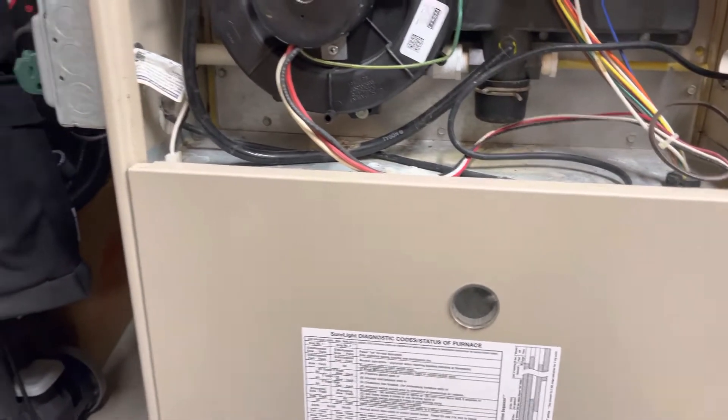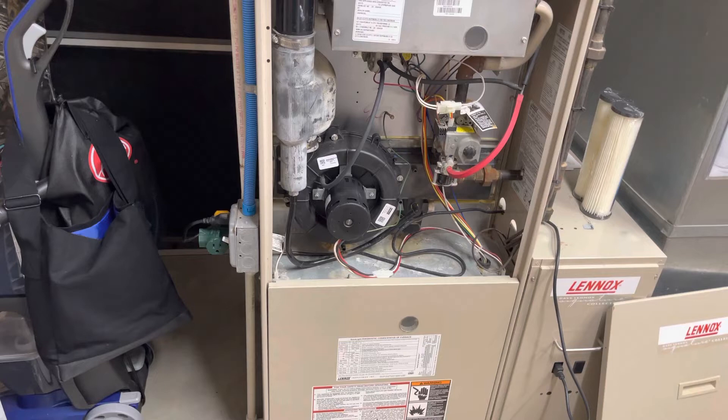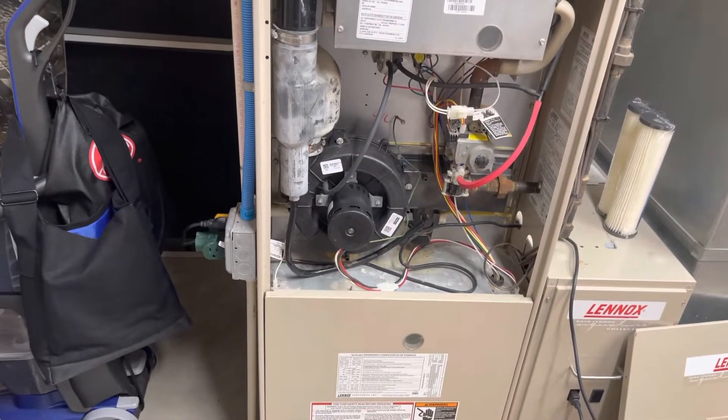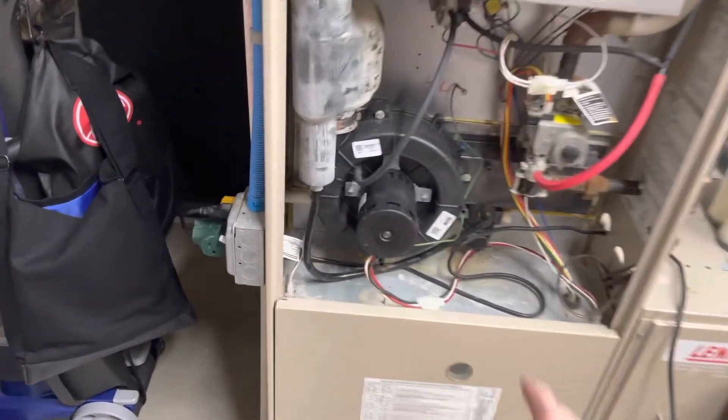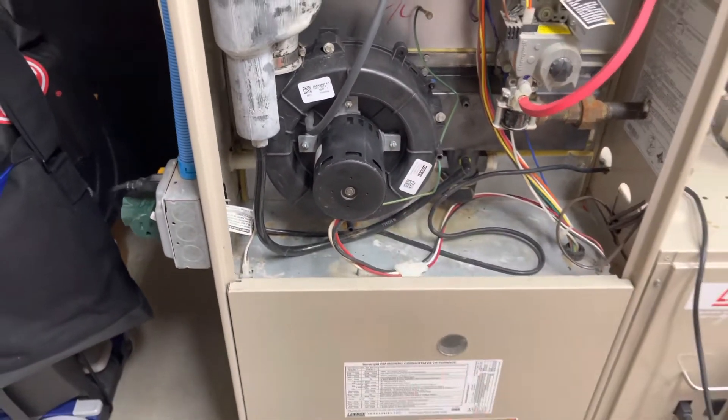As you can see, it is up and running fine now. The root cause was water over the summertime — or condensation — collecting in this fan housing right here.